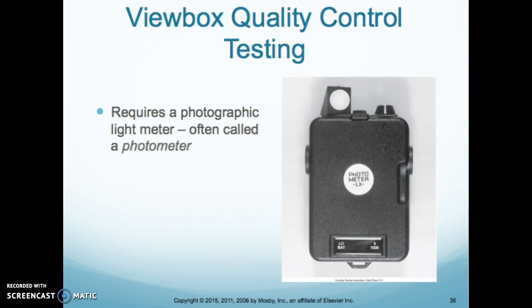This is a photographic light meter, also called a photometer. We use this to measure the light coming out of the view boxes.